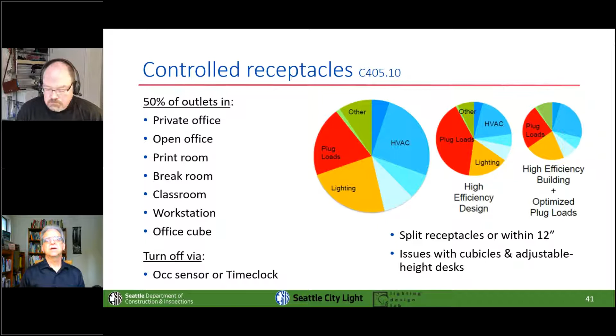Feedback I've had is that split receptacles work best so that everybody knows that the top outlet turns off on weekends, but you can also have pairs of controlled and uncontrolled outlets within 12 inches of each other. Finally, a lot of us are getting these ergonomic adjustable height desks now that have their own outlets built in, and these are typically just plugged into the non-controlled power. But that's a problem I guess we'll have to resolve in a different code cycle.